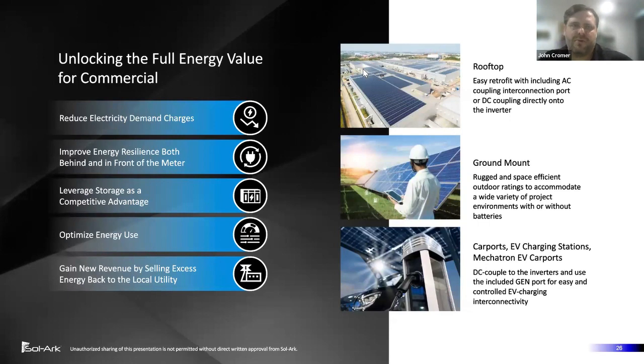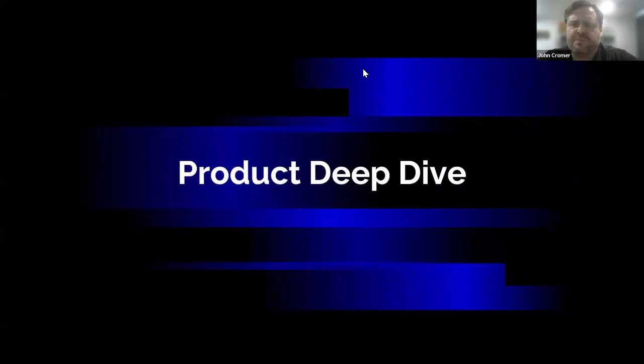Your utility transformer coming from the grid, you can land the grid port onto that, and you may not even use the load port. It might be a non-backup project, or you can run the conduit and put the load port there for future use, or go ahead and tie it in and do building backup. But the point is, on a carport, the unique aspect of a Sol-Ark hybrid inverter is that all elements of the system, the solar array, the grid connection, the backup load connection, the EV charging station, can all be tied into that inverter at a single point, which dramatically simplifies the switch gear and interconnection hardware for that infrastructure.